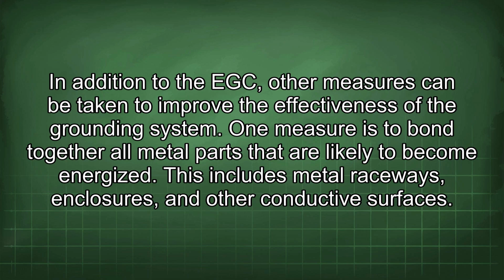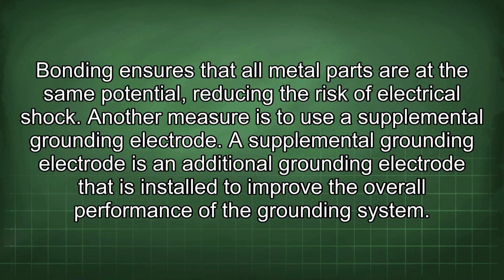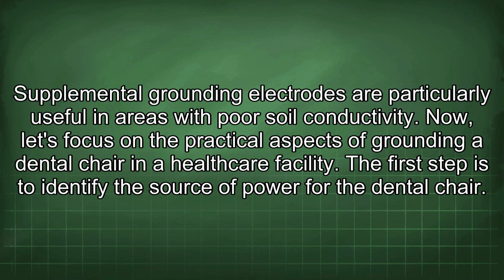One measure is to bond together all metal parts that are likely to become energized. This includes metal raceways, enclosures, and other conductive surfaces. Bonding ensures that all metal parts are at the same potential, reducing the risk of electrical shock. Another measure is to use a supplemental grounding electrode. A supplemental grounding electrode is an additional grounding electrode that is installed to improve the overall performance of the grounding system. Supplemental grounding electrodes are particularly useful in areas with poor soil conductivity.